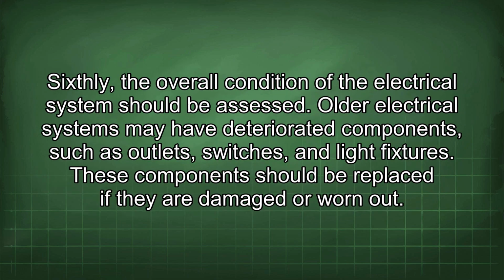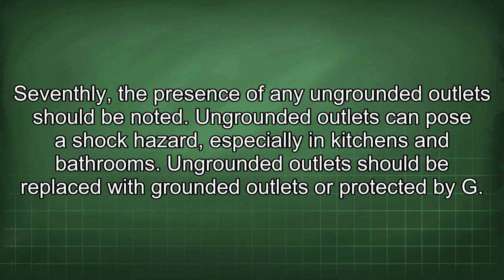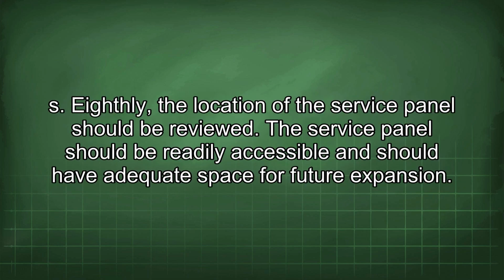Sixthly, the overall condition of the electrical system should be assessed. Older electrical systems may have deteriorated components such as outlets, switches, and light fixtures. These components should be replaced if they are damaged or worn out. Seventhly, the presence of any ungrounded outlets should be noted. Ungrounded outlets can pose a shock hazard, especially in kitchens and bathrooms. Ungrounded outlets should be replaced with grounded outlets or protected by GFCIs.